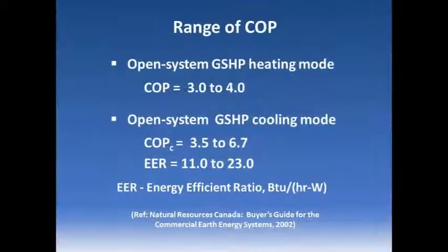But in reality, in the utilization of heat pump systems, based on the currently available ground source heat pump systems, we use the COP. In this study, we use a COP in the range between 3 and 4 for our calculations. And for the cooling mode, we use a COP between 3.5 and 6.7. In America, people usually use the EER, which is the energy efficiency ratio. In this case, it has a unit: BTU per hour per watt of input electricity.